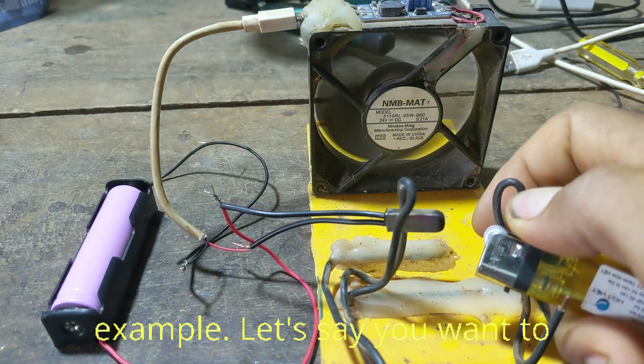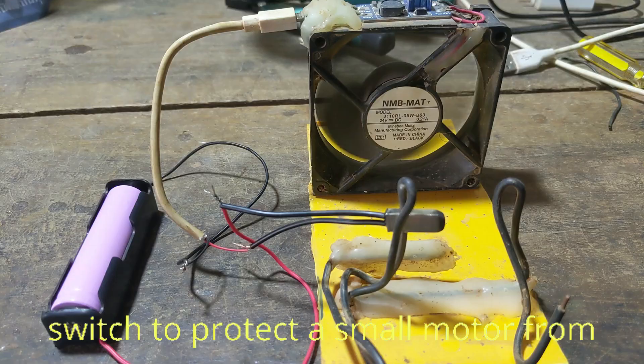Installation example: Let's say you want to install a KSD 9700 NC switch to protect a small motor from overheating. Choose the right rating: select a KSD 9700 with a temperature rating suitable for your motor, for example 80 degrees Celsius.